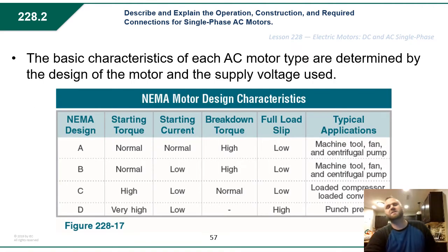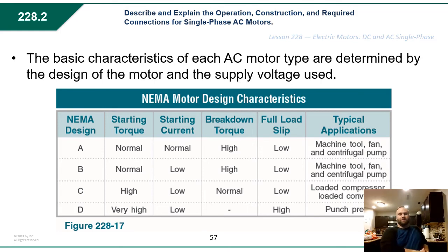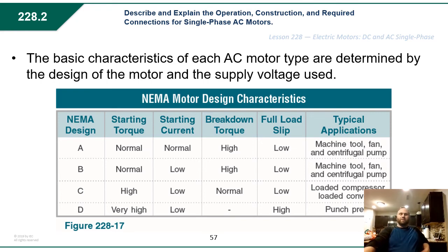The basic characteristics of each AC motor type are determined by the design of the motor and the supply voltage used. NEMA has four different designs for AC motors: A, B, C, and D. Each one has different starting torques, starting current, breakdown torques, full load slip, and typical applications. Know your NEMA designs — when replacing a motor, always check the nameplate for which NEMA design it is.